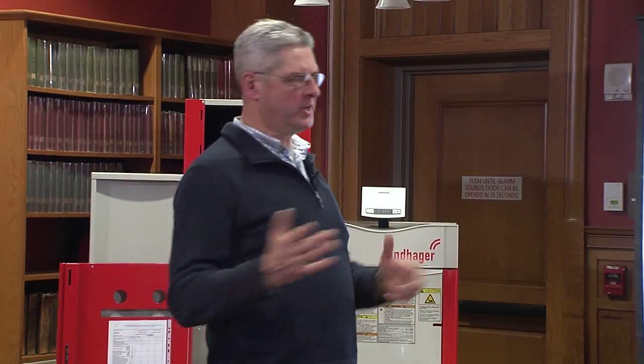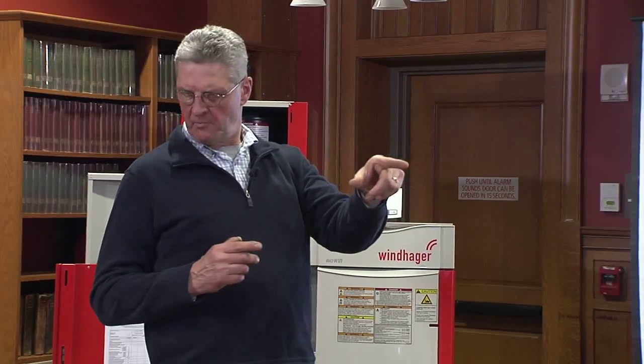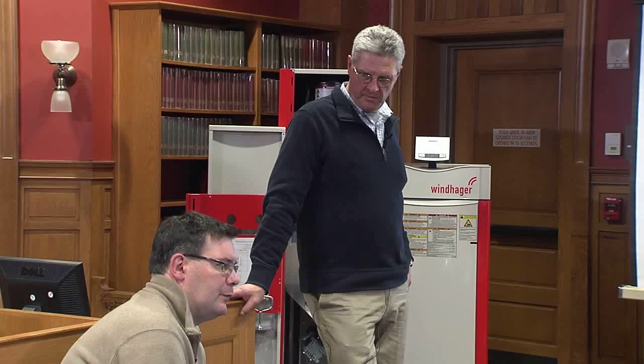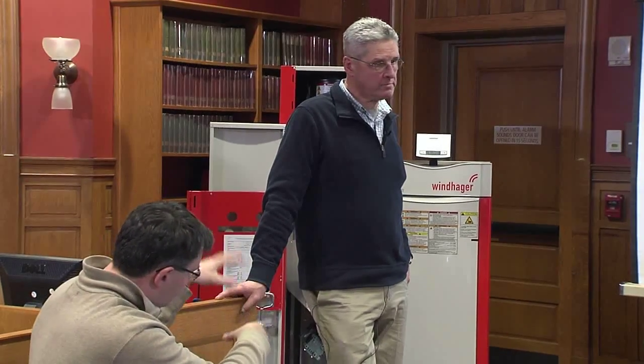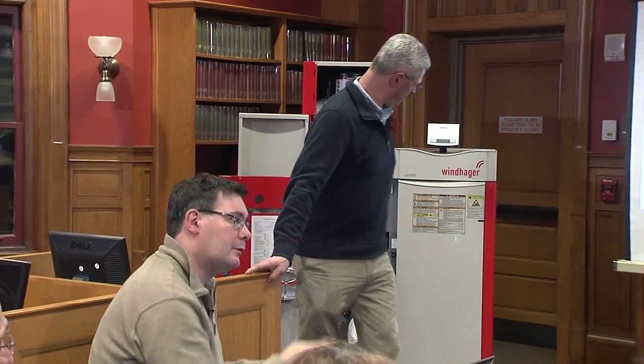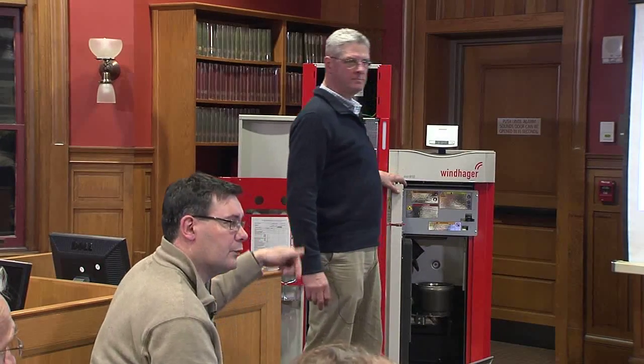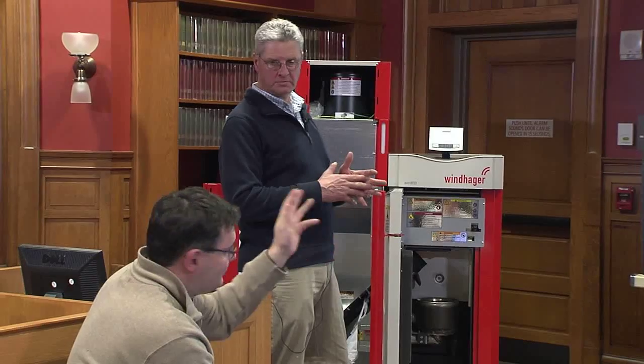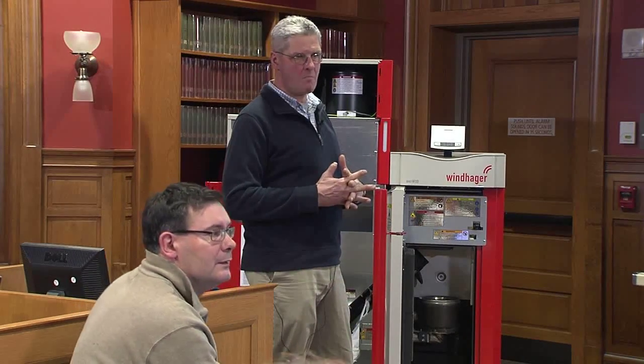This one here, and you'll see that on, well, there are two different brochures there. There's the current residential one, which is a 2.9 to 3.5. So there's four models, 89,000 BTU, 72,000 BTU, 51,000 BTU, and 35,000 BTU. They all look the same, footprint is the same, just the two biggest ones have this size burn pot, the two smaller ones have a burn pot about half the size. The heat exchanger inside also has less steel for the two smaller, but they look identical. The price difference is only $200, $300. It's the same unit, so it can be sized up or sized down depending on what you have.